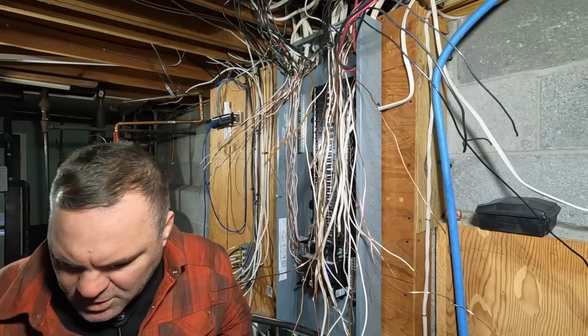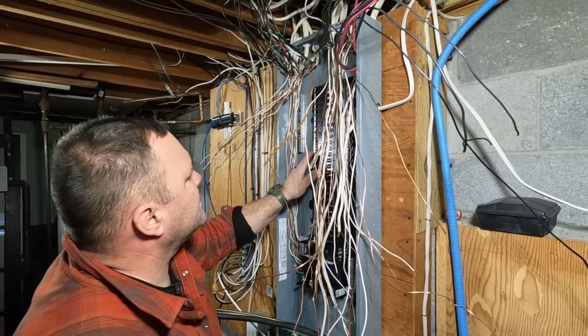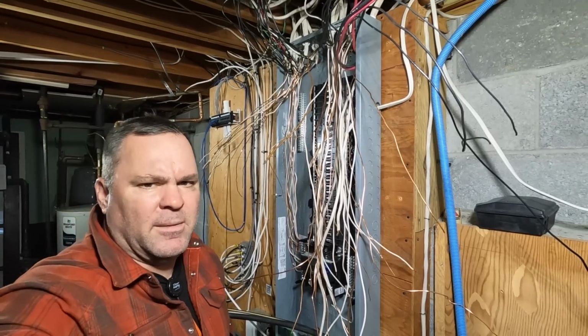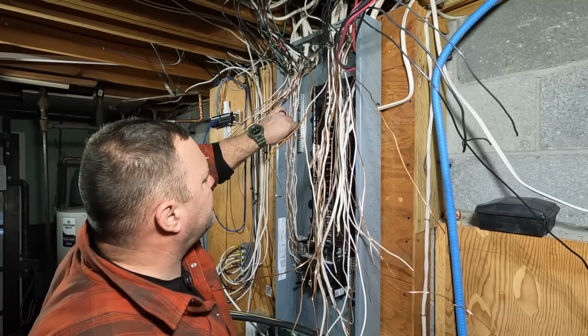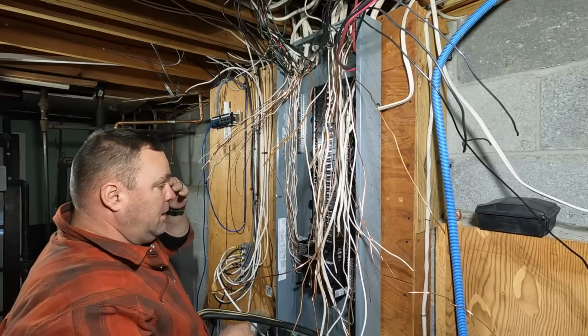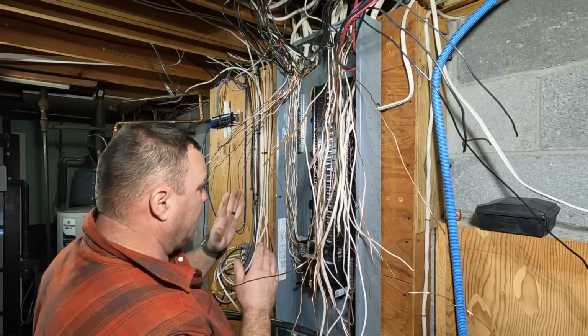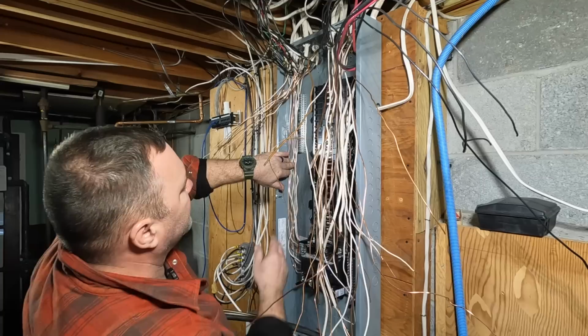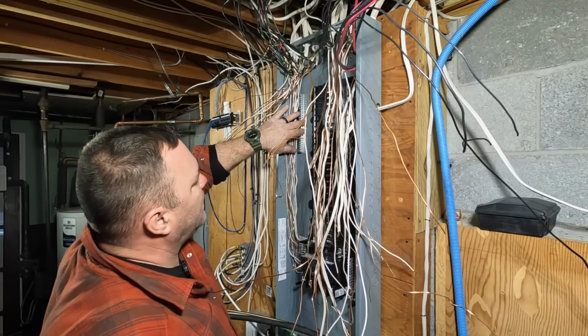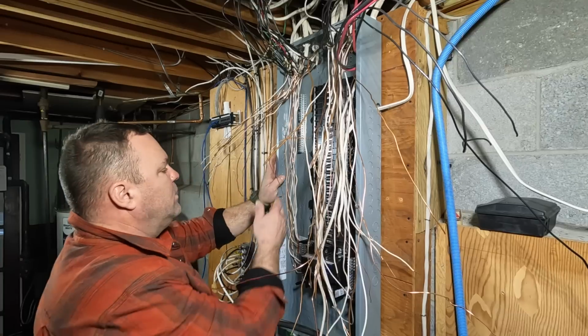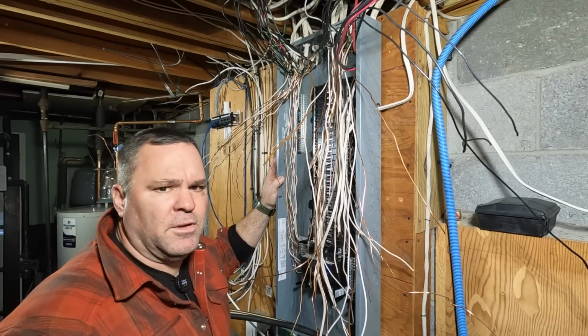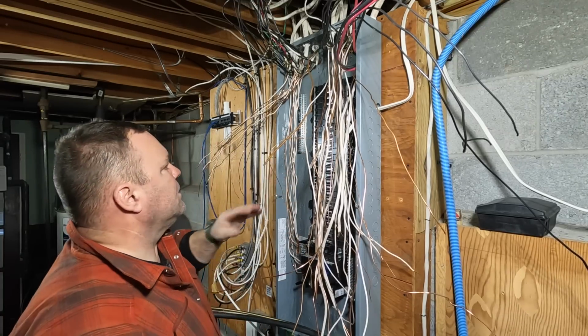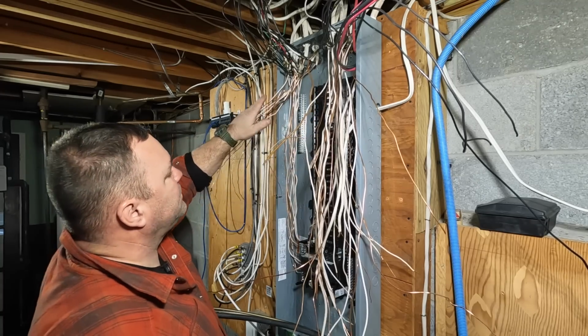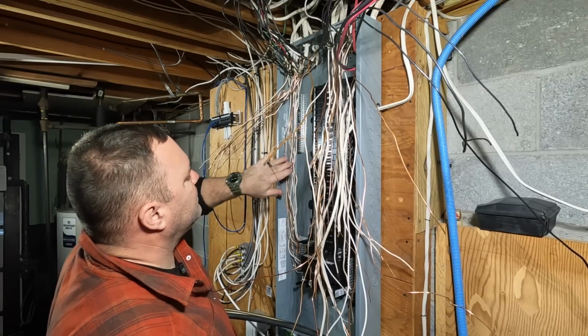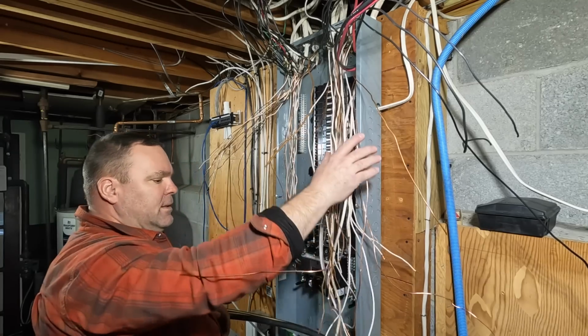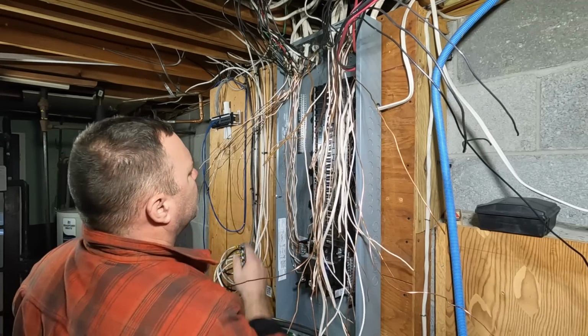So the article I'm going to post is definitely in chapter 2. But basically what it says, and I failed an inspection one time because I did not notice at the time, is that because we bond our neutrals and our grounds in this panel, everything in this panel is at the same potential, okay? The thing is, the neutral is a current carrying conductor, and because this bus is attached to the enclosure right now, we can't use the enclosure as a path for the neutral current in the circuits. What we're going to do is hook up a bunch of neutrals over here and grounds, and the grounds can be doubled up, which we're probably going to do, and a lot of these that don't reach the bus down here are also going to be over here.